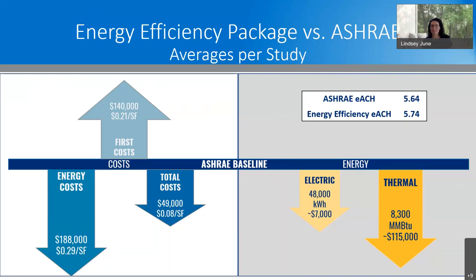However, when you combine the implementation costs and the energy impact costs together, the energy efficiency package is more effective than the ASHRAE package by about $49,000. On the energy impact side, the energy efficiency package saved more electric and thermal energy than the ASHRAE package by about 48,000 kilowatt hours and 8,300 MMBTUs respectively, which equates to about $7,000 in electric cost savings and about $115,000 in thermal cost savings. So the top energy savings measures in comparison to the ASHRAE baseline were reduced outdoor air, non-IAQ measures, reduced building flush time, and control optimization.